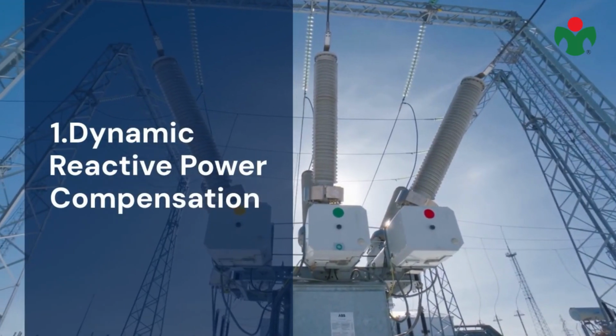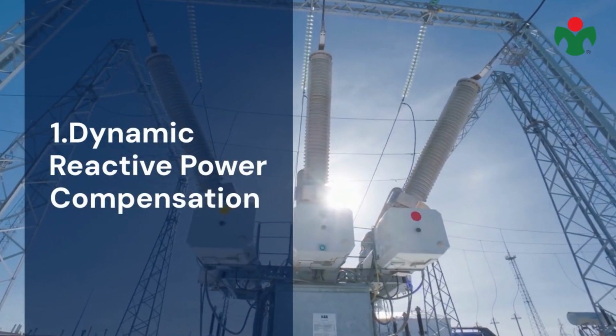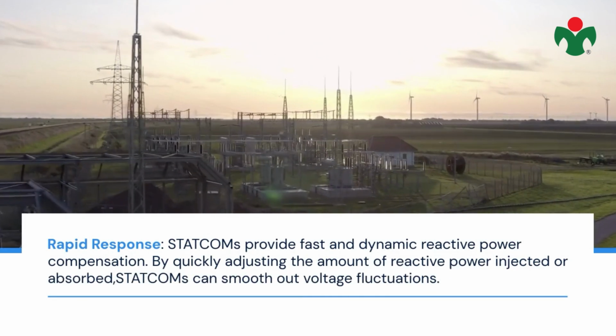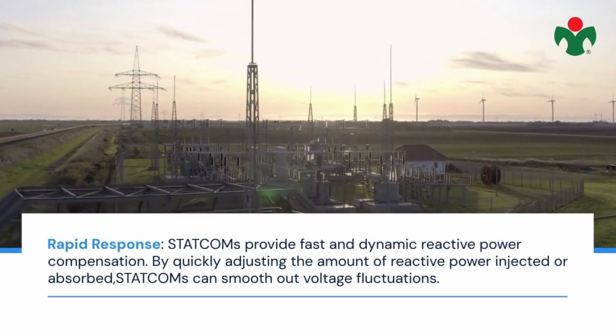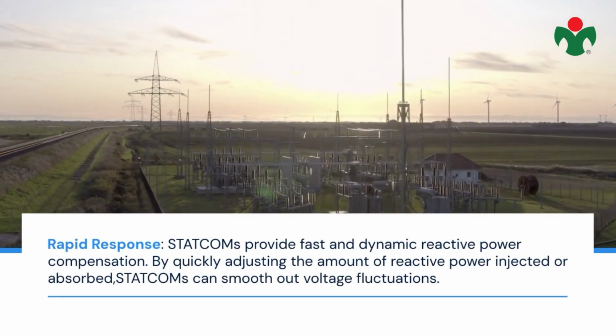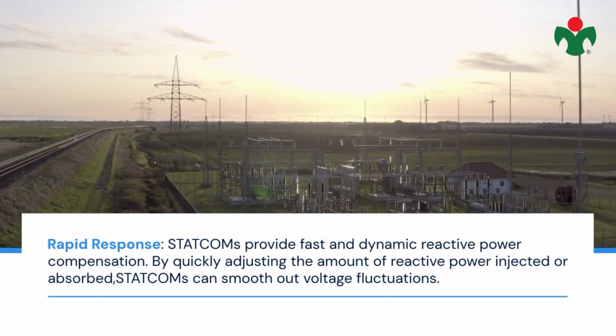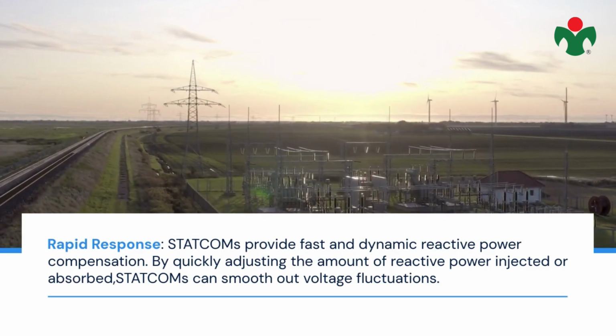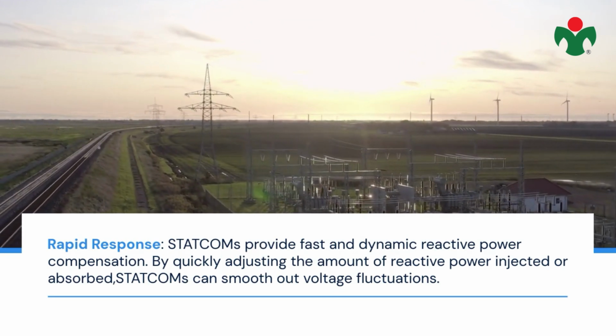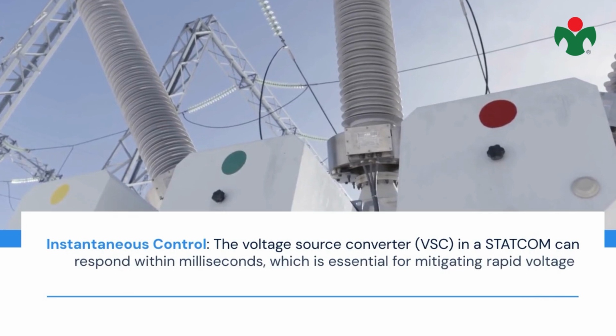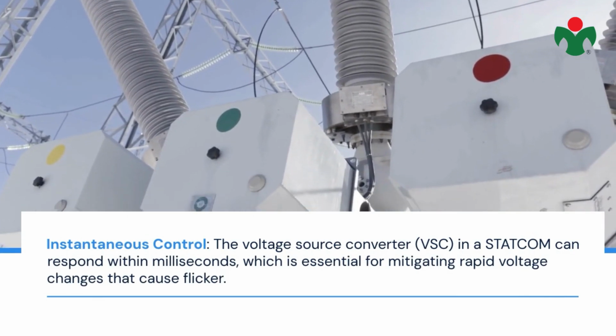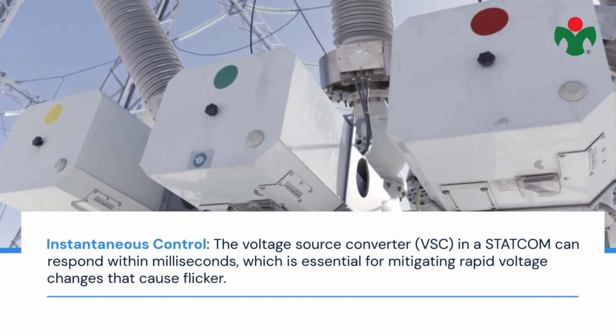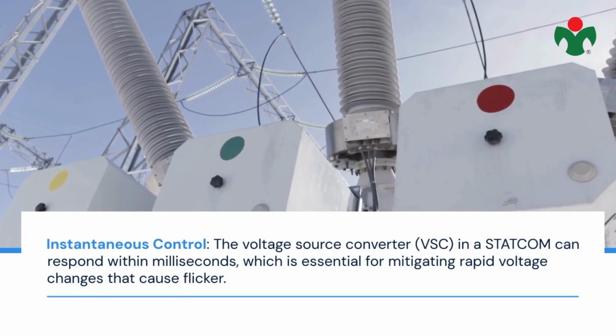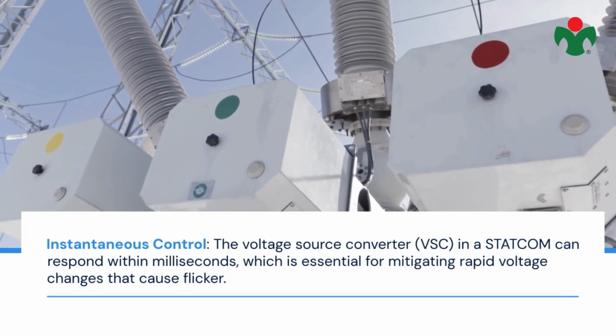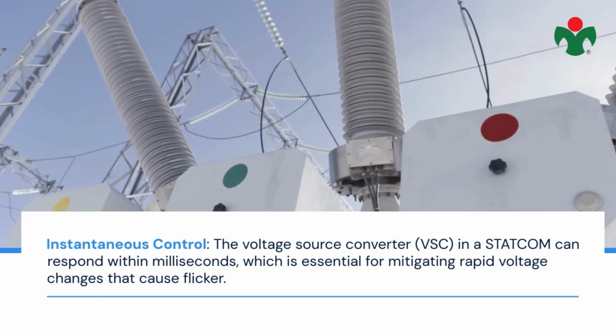1. Dynamic reactive power compensation. Rapid response. STATCOMs provide fast and dynamic reactive power compensation. By quickly adjusting the amount of reactive power injected or absorbed, STATCOMs can smooth out voltage fluctuations. Instantaneous control. The voltage source converter, VSC, in a STATCOM can respond within milliseconds, which is essential for mitigating rapid voltage changes that cause flicker.